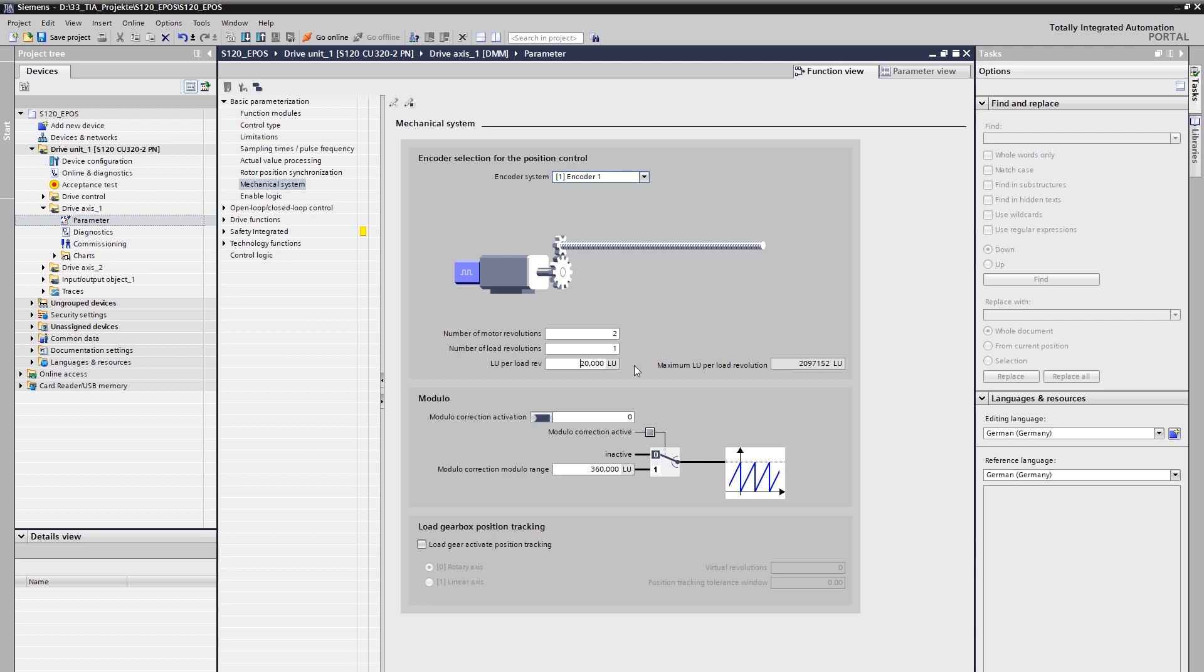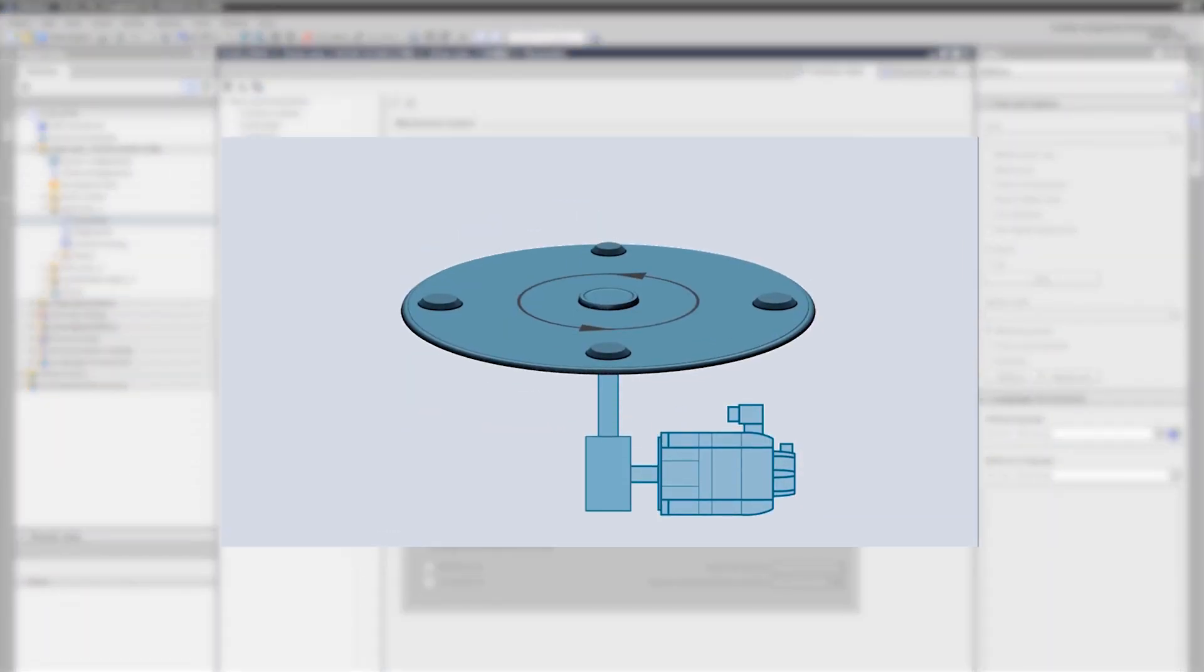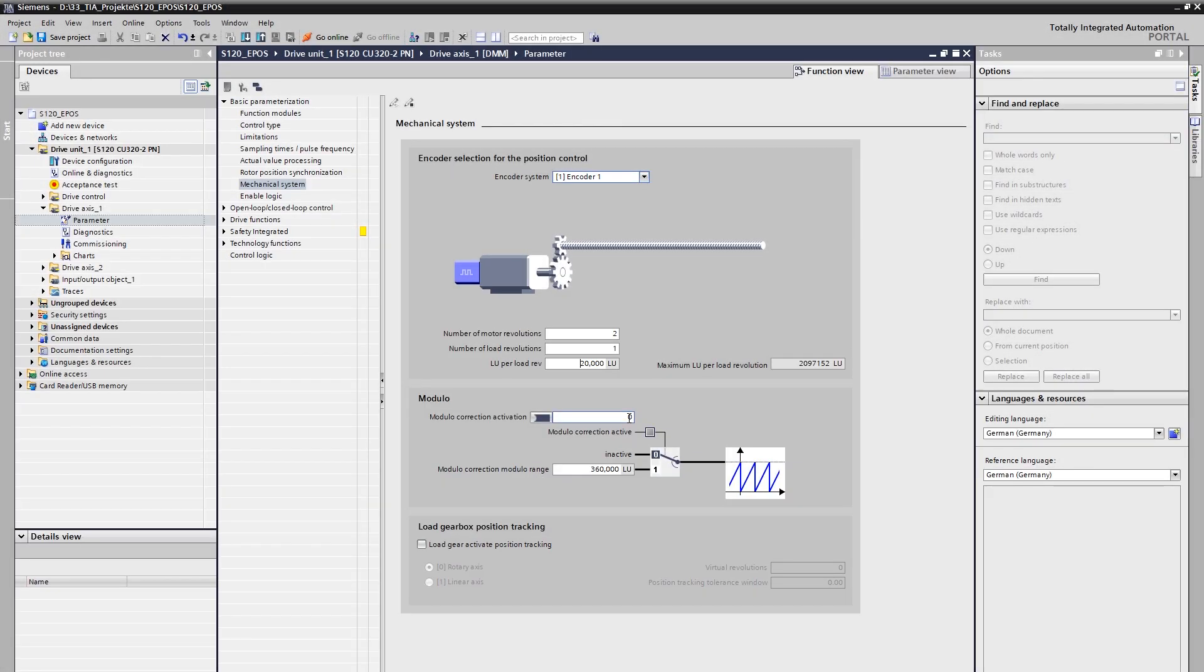In the case of a rotary axis or an endlessly turning axis, the next step is to make the setting for modulo. Modulo correction is always required and activated when a mechanical system is involved in which the position is repeated physically and does not rise endlessly. These can be different mechanics, examples are rotary knives, rotary transfer tables, chain drives and many more. The modulo range is the value at which the position is repeated and returns to zero or, in other words, the value at the start position and end position are exactly the same location. With a 360 degree axis with a resolution in milli degrees, the modulo range would also be 360 000 LU. If the mechanics have moved forward one revolution, the position starts at zero again after 360 000 LU and is exactly at the same position. In our application we have a linear movement via a spindle, so the activation at this point is not necessary.